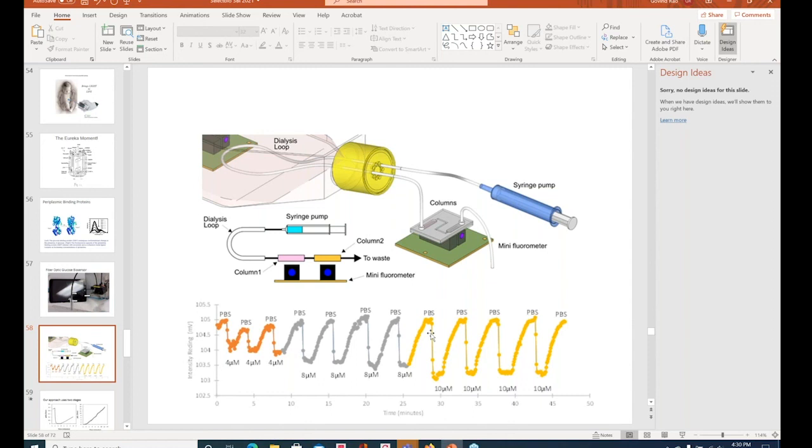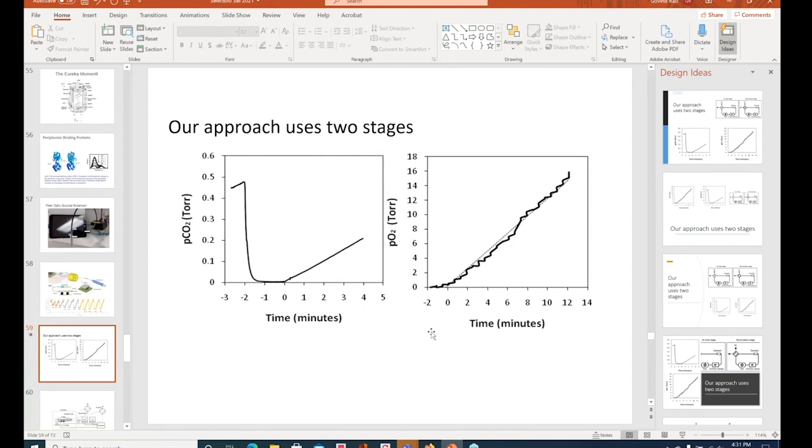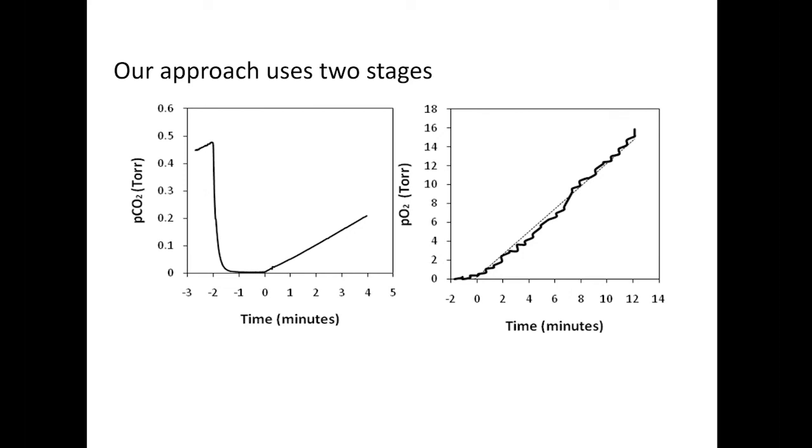The other thing we do is also measure respiration rate. Our approach uses two stages. So you put the sampler against the skin of the baby, and you flush it with nitrogen. What that does is give you a zero baseline. And then you flip a valve, and then you just recirculate the gas. So what happens is oxygen and CO2 in the blood of the patient diffuses across and is measured by the sensor. So in a few seconds, you're able to measure the diffusion rate. And if you do the math, the diffusion rate is proportional to whatever the concentration in the blood is.